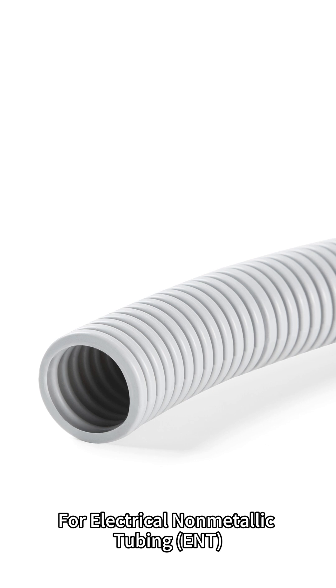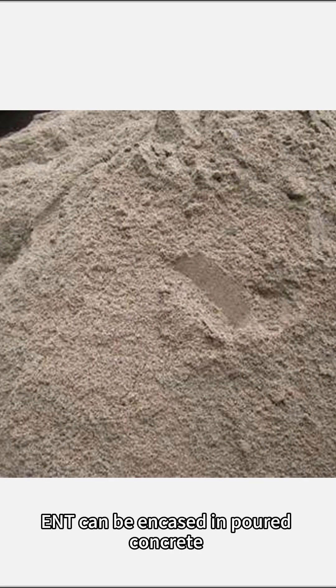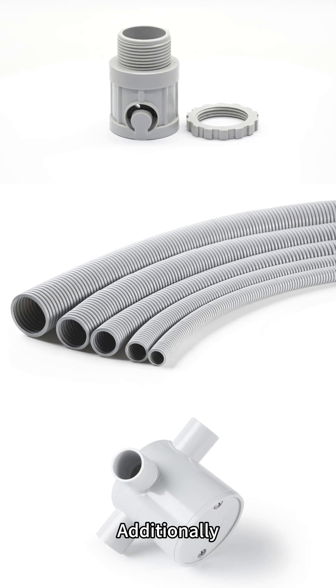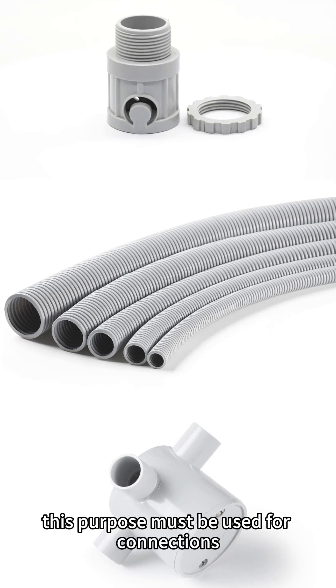For electrical non-metallic tubing (ENT), NEC Article 362.10 Uses Permitted states that ENT can be encased in poured concrete or embedded in a concrete slab on grade, provided it is placed on sand or approved screenings. Additionally, fittings specifically identified for this purpose must be used for connections.